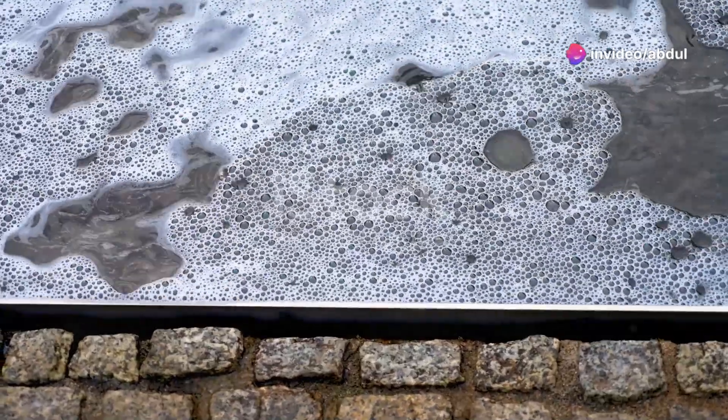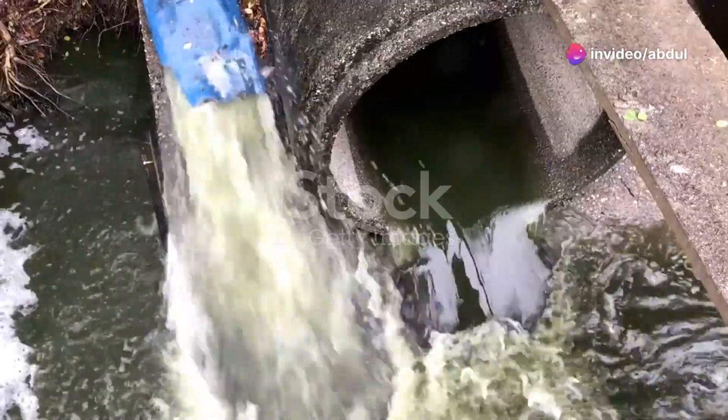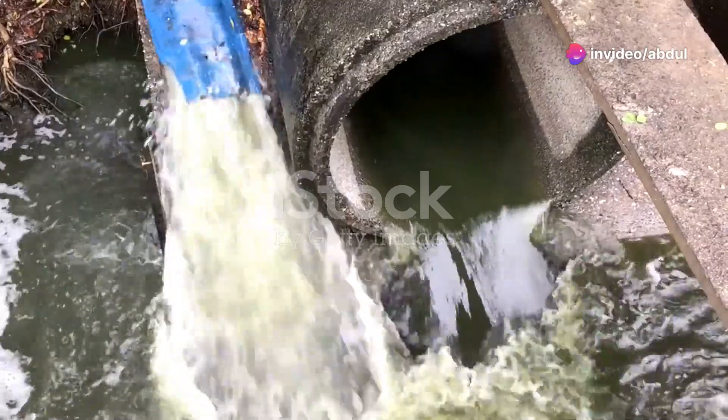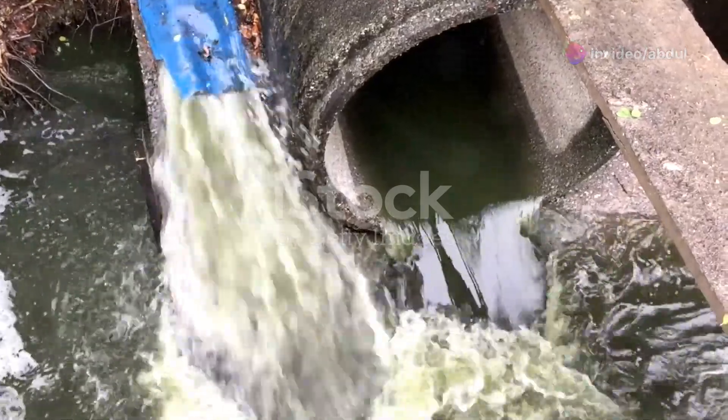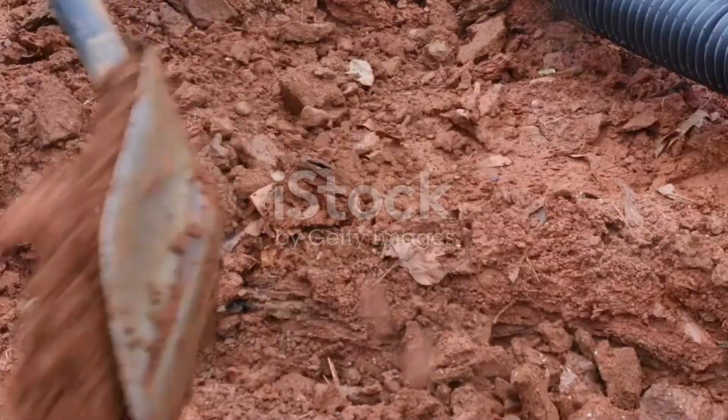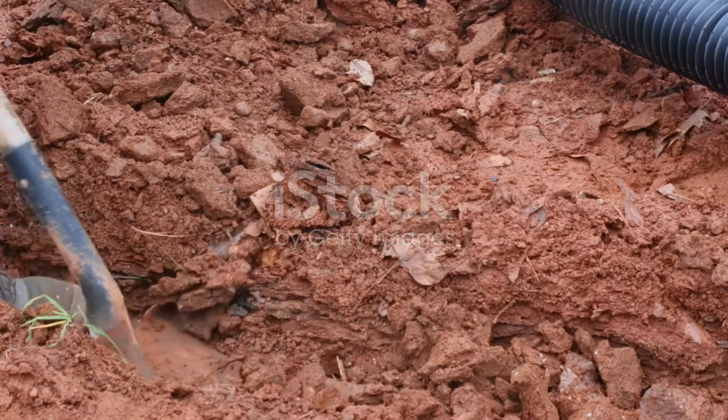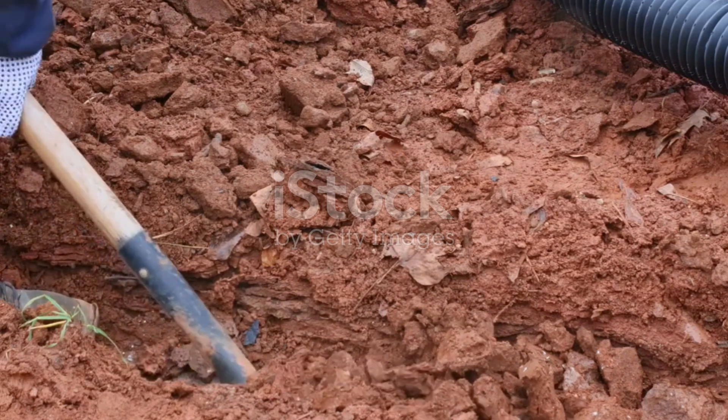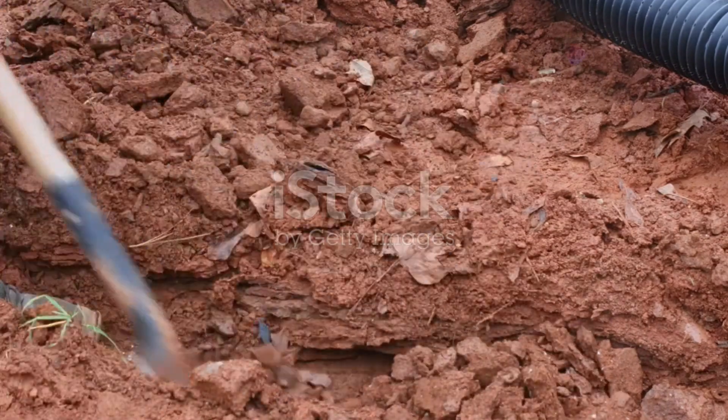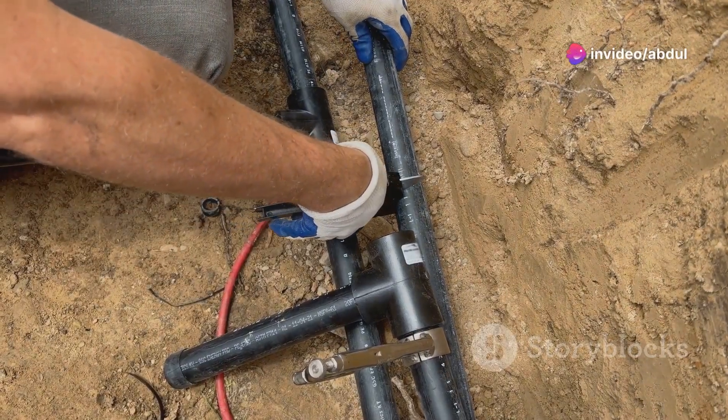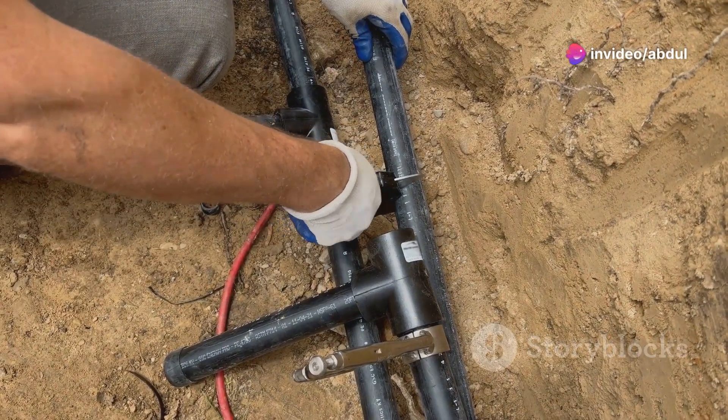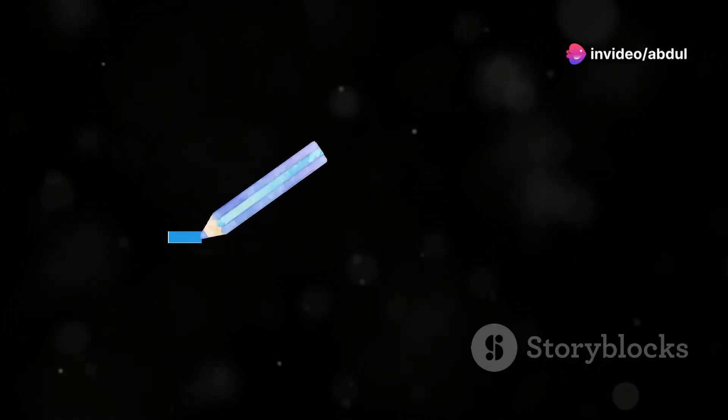Drainage systems rely on gravity to carry wastewater away from fixtures and into the sewer system. When drawing drainage lines, you need to consider the slope or gradient of the pipes to ensure proper flow. A general rule of thumb is a quarter-inch slope per foot of pipe.